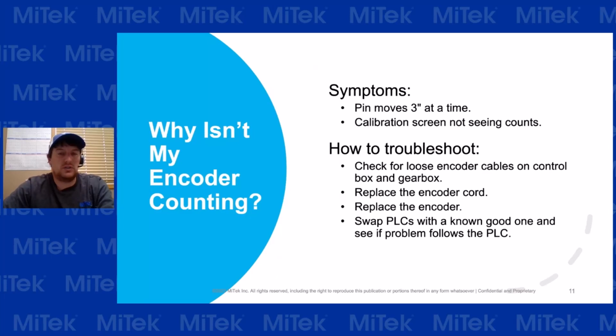Very rarely do you see a PLC make it do that, but at times the counts aren't getting through into the PLC. If you've swapped out the encoder cable, swapped out the encoder, swap the PLC to the one to the right and see if it moves with the PLC at that point in time. If not, there could be some deeper issues, and I would say to call us.